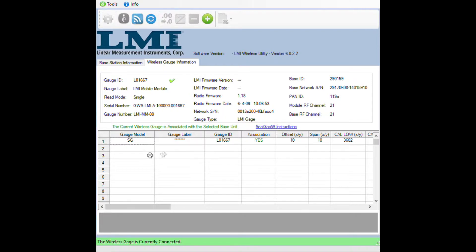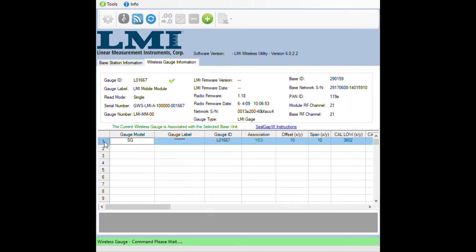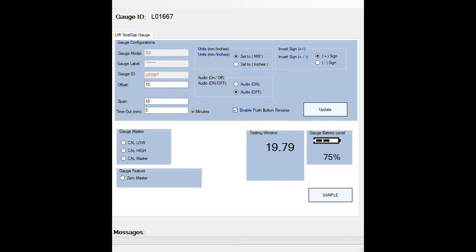Now, to enter the calibration screen, simply double click on the number 1 next to SG. After a few seconds, your screen will go blank and another screen will appear. This is your calibration screen. Here you can calibrate or simply zero your gauge and also set your offsets and span in this window.